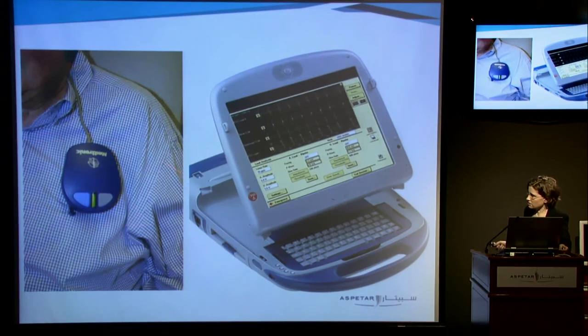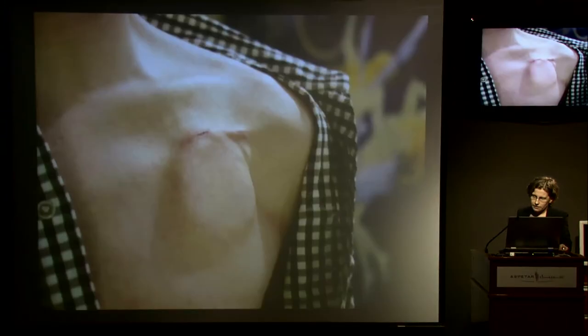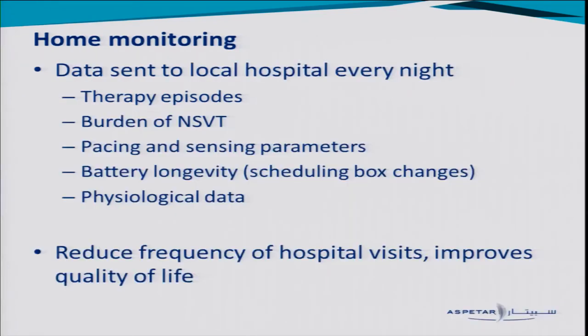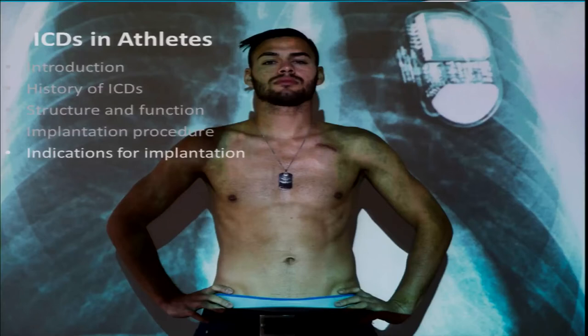The device is interrogated remotely — you put a wand over the device, a non-invasive procedure, and it communicates with a computer, showing marker channels and surface ECG. For long-term follow-up, patients are now monitored at home with a bedside device that communicates with the ICD every night, sending data to the hospital. Every morning technicians check downloads from all patients to confirm there've been no therapies and no lead problems. This has revolutionised ICD follow-up — we get data about therapy episodes, burden of non-sustained VT, pacing and sensing parameters, and battery status to schedule box changes.